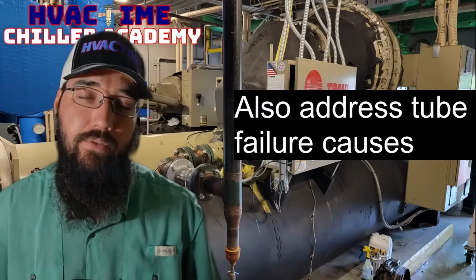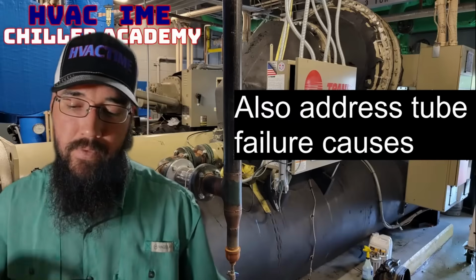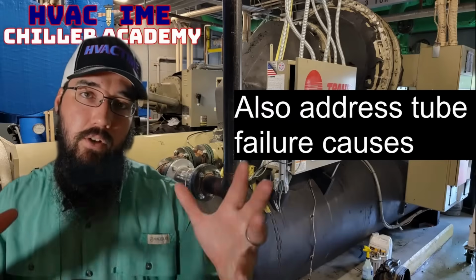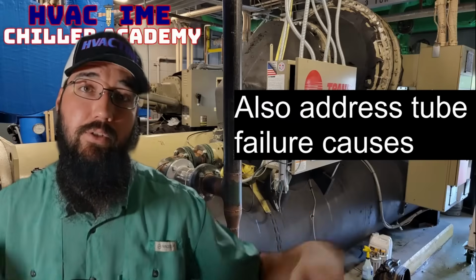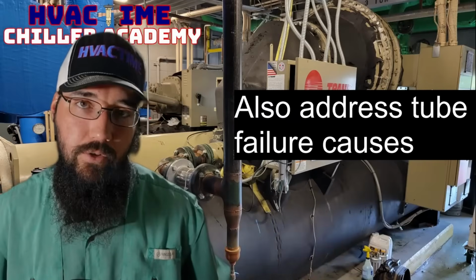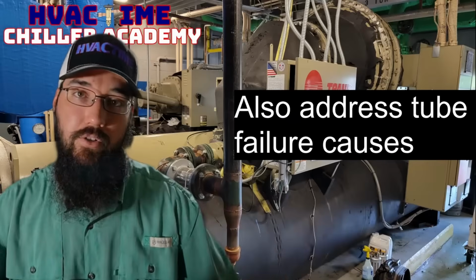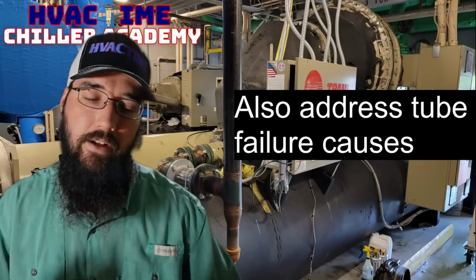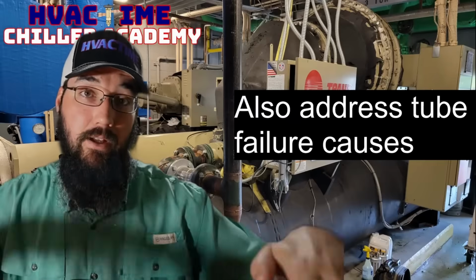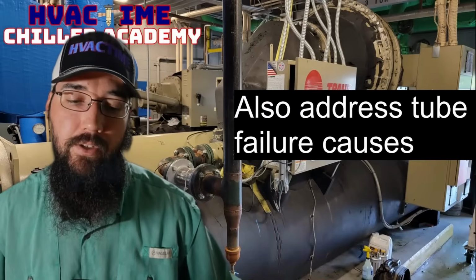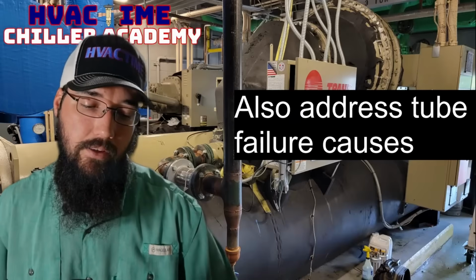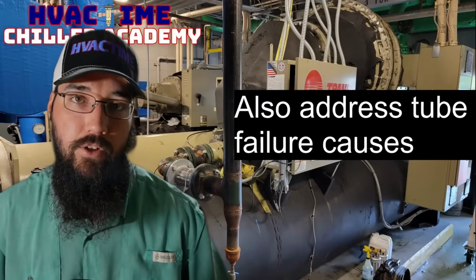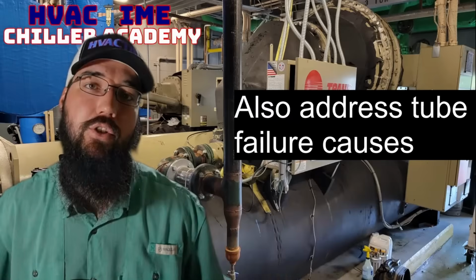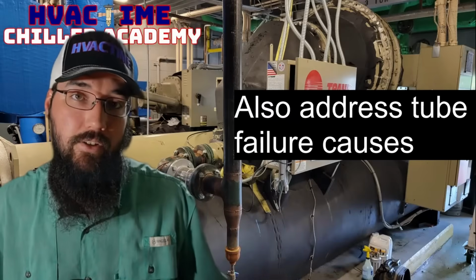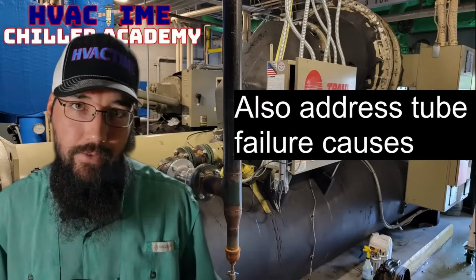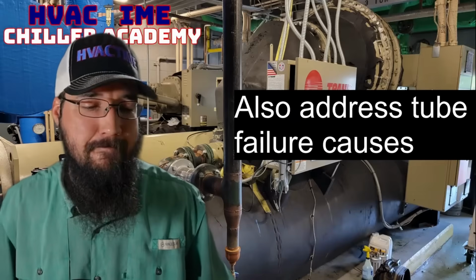Now, if you had a catastrophic failure, which I've seen some of these where it literally floods the chiller. So first of all, if it's a high pressure machine, the refrigerant's going to flow out into the water circuit, but a low pressure machine, water's just coming straight in. And so in a catastrophic event, I've had pictures sent to me of CVHs where the water level was up into the suction nose cone, just at how much had filled up in the chiller and then sat there on top of that. So that would be catastrophic. That'd be the definition of catastrophic.